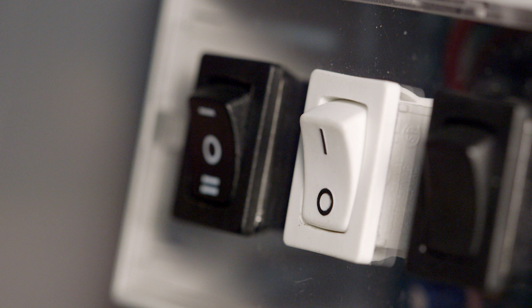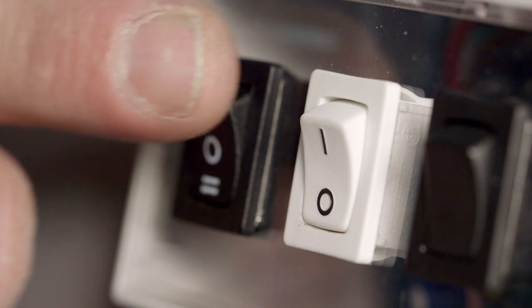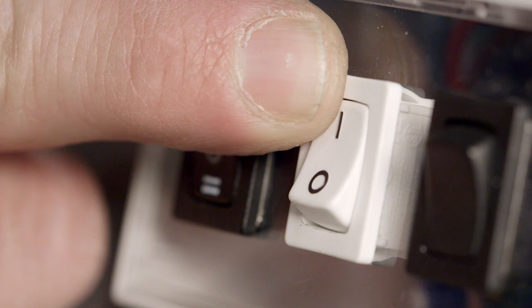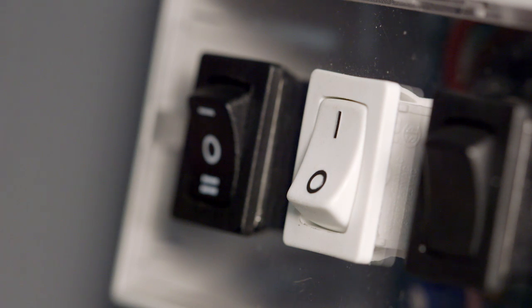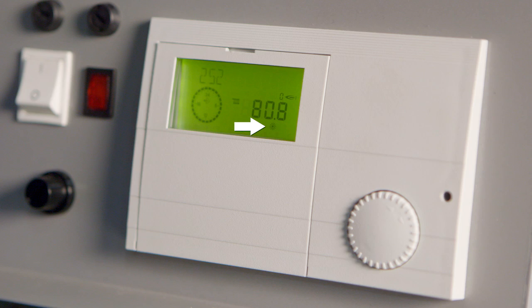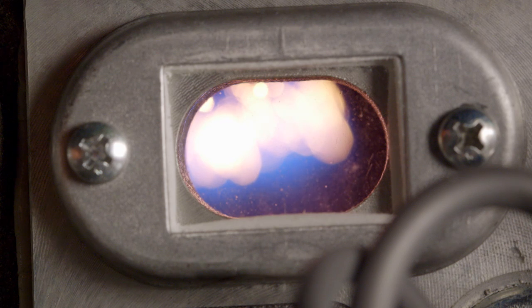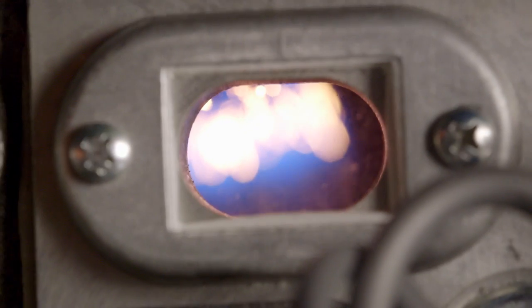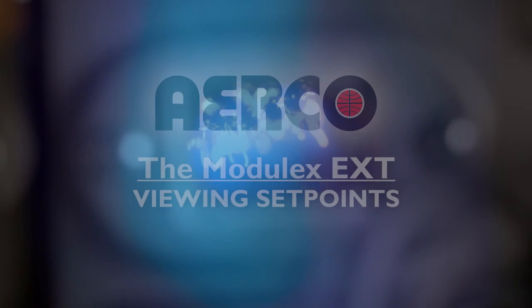Second, there is a 2-position rocker switch on the BCM that determines whether or not the BCM can act as a backup controller. 0 position means no. 1 position means it will take over control if the E8 fails. Finally, double check to make sure the E8 is in the correct mode. Take one last look to make sure that you observe accurate operation that ensures a burner light upon demand.